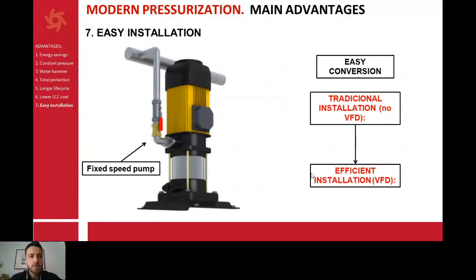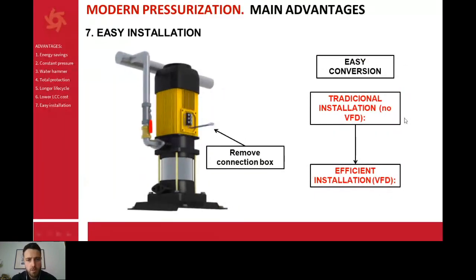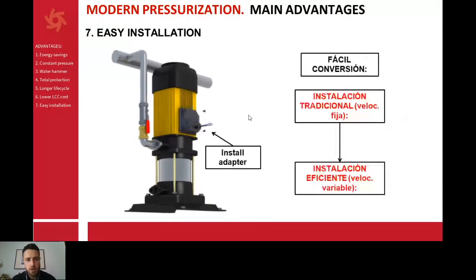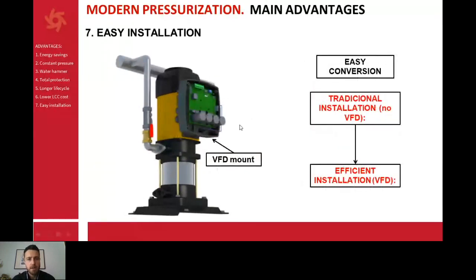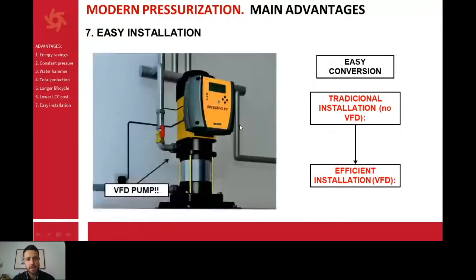And what about the installation? In case we have a fixed speed pump, it's very easy to convert it into a variable speed pump. How can we do it? We remove the connection box, we install the adapter, we mount a VFD, and we already have a VFD pump. Incredible. And don't forget to also install the pressure sensor. And we already have a modern pressurization system.